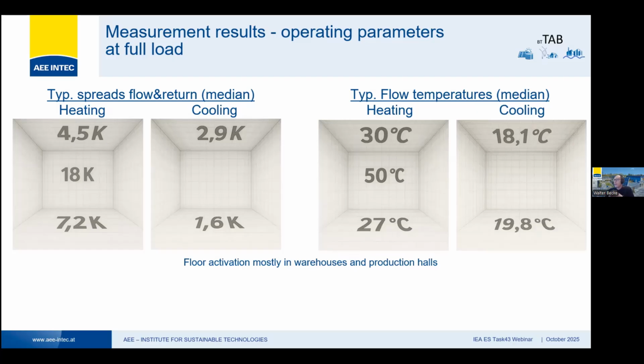So you see at full heating load, in that case, 50 degrees centigrade were needed to make the room inside comfortable. For the floors, you see a higher temperature difference than for the ceilings. The reason is that the floor activation was mostly used in warehouses and production halls. So they are usually less insulated than office buildings or residential buildings or rooms. And that results in a higher temperature difference for heating. On the cooling side, you have a smaller temperature difference. That's usually because the comfort requirements or the temperature requirements for halls, production halls and warehouses are lower than for office or living rooms.